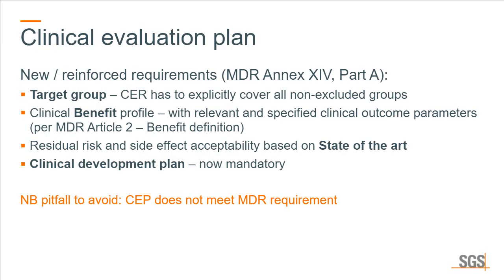When we look at the clinical evaluation plan, there's a couple of new or reinforced requirements. It is very important to point out the target group. The clinical evaluation report has to explicitly cover all non-excluded patient and user groups.